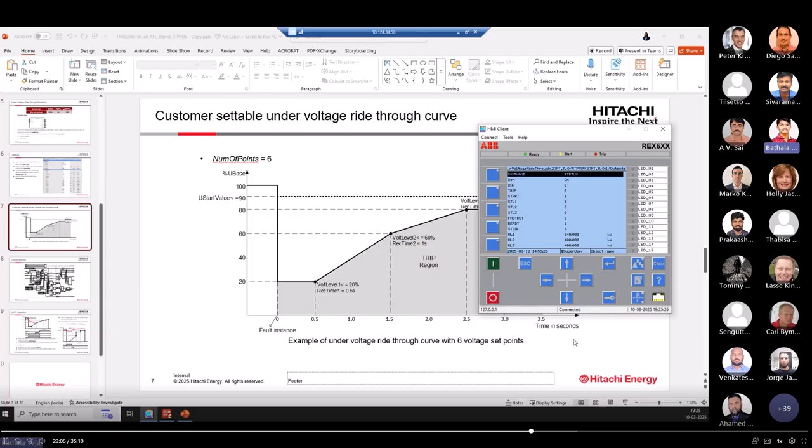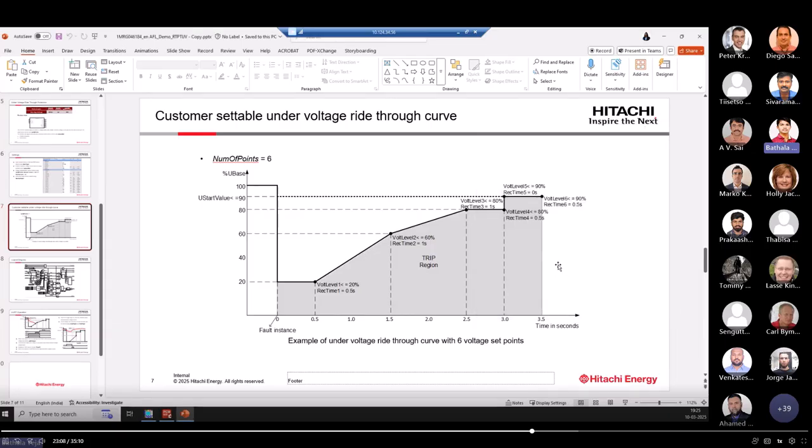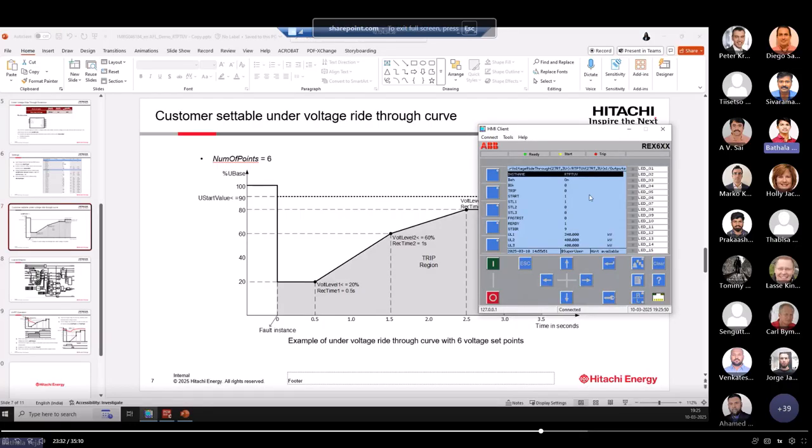There are two conditions to reset start. Both have to be satisfied. One, the entire curve has to complete. The other, at the end of the curve, the voltage should be higher than the last recovery voltage. That is 90% in this example. It is not greater than 90%, so that's why these are still high. So I apply rated voltage again now. You can see all are resetting now. So the function is set for looking for another under voltage condition. That's how it works.